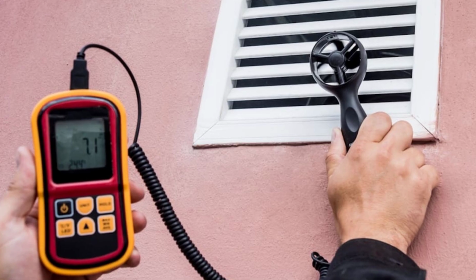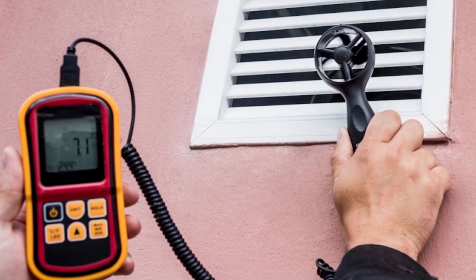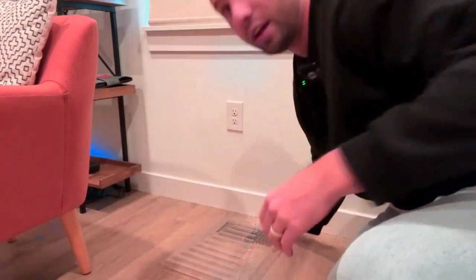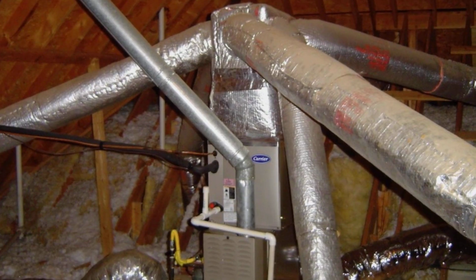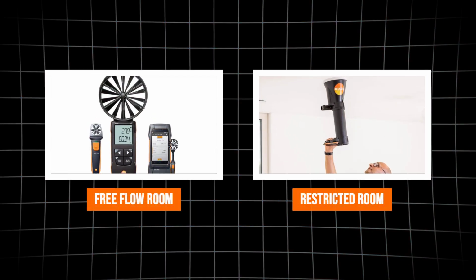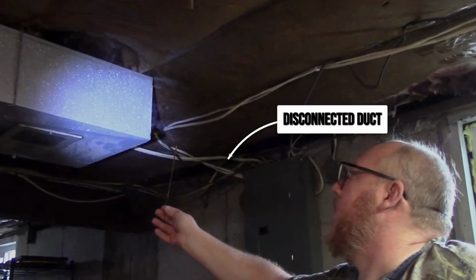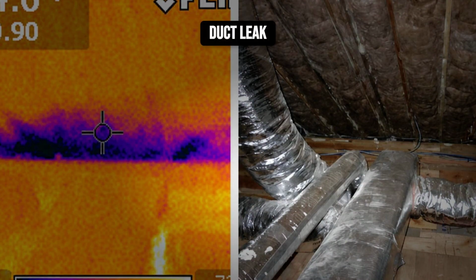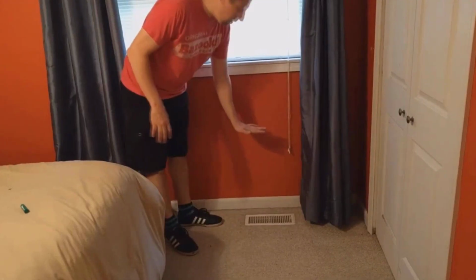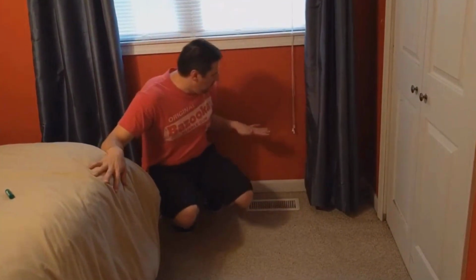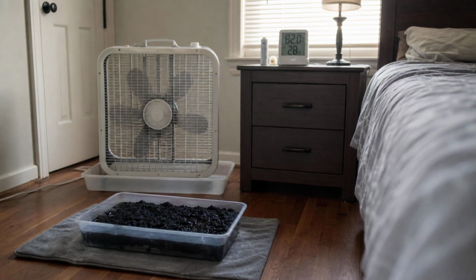First, I would check whether enough conditioned air is reaching the room. Is the supply register fully open? Is furniture blocking it? Is the duct disconnected, crushed, leaking, or undersized? Is the room far from the air handler? Does the airflow feel noticeably weaker than it does in other rooms? A disconnected duct in an attic or crawl space can dump expensive conditioned air outside the living area. Meanwhile, the room receives very little cooling. No tray of charcoal will solve that.